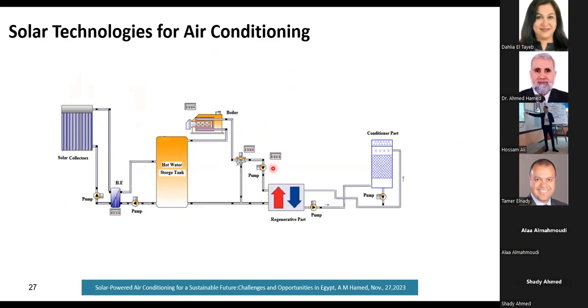The liquid desiccant system is another version of a solar-powered dehumidification system. In this case, we use a liquid desiccant, for example, lithium bromide, lithium chloride, calcium chloride, and others, for the purpose of absorption of humidity from the humid air. And then we may also use vapor compression in hybridization with the desiccant absorption system.